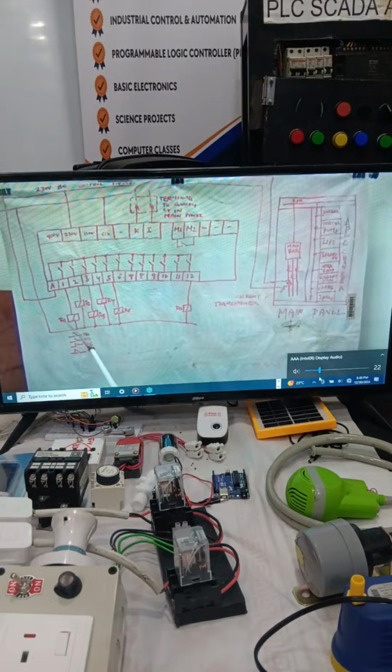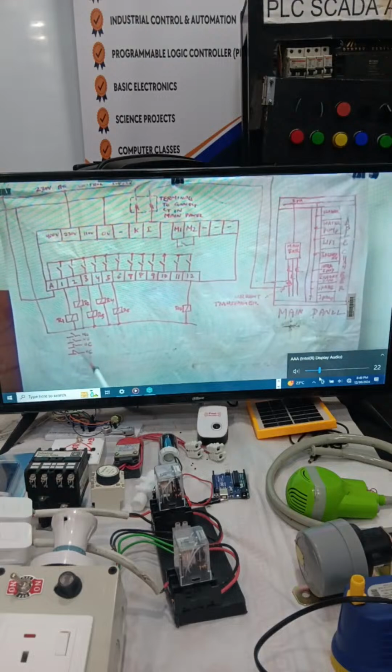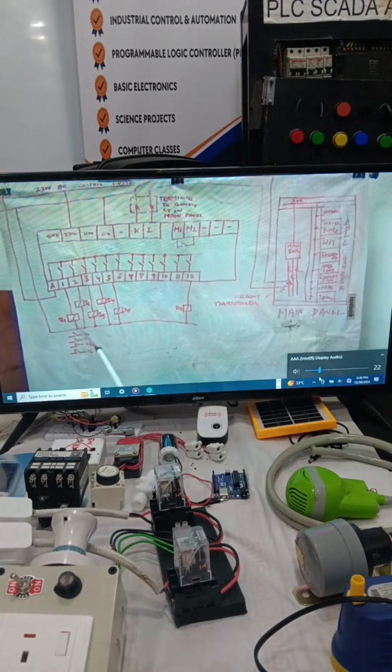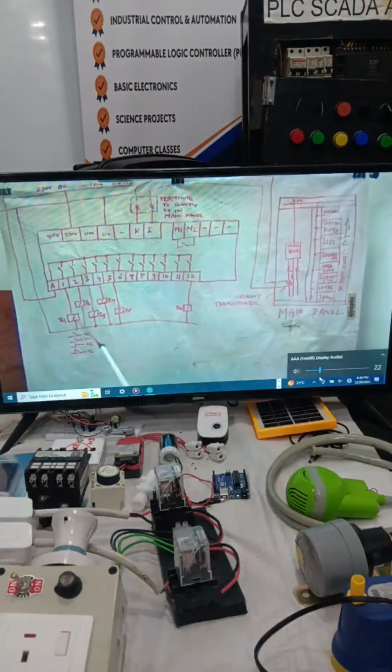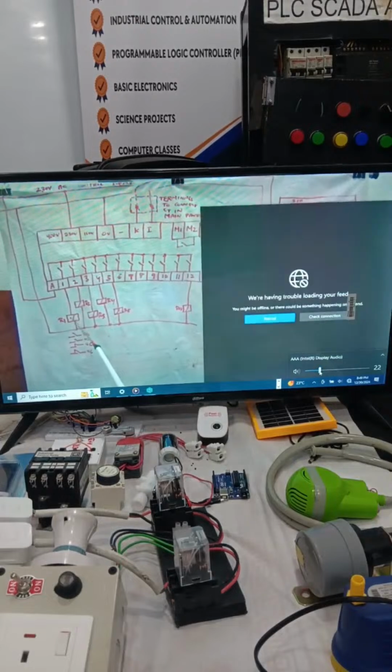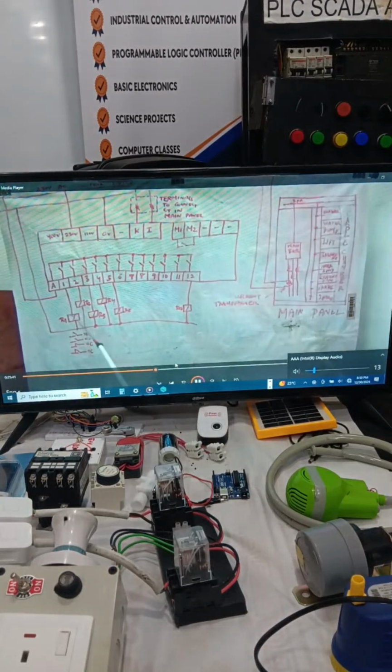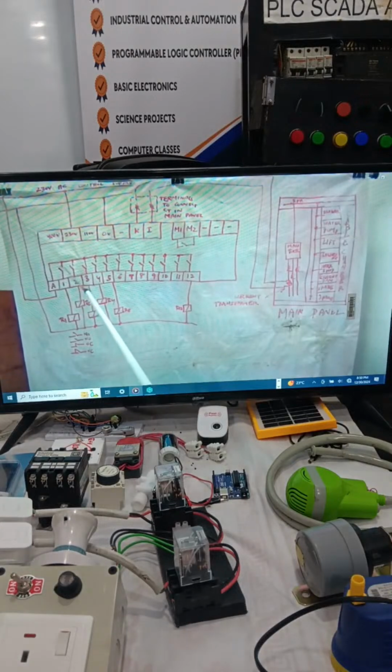In some cases, if the contactor size is small, it directly feeds the contactors. But if the contactors are big, or there are more contactors, like in our case where we have 3 contactors in parallel, the load comes to this point. In that case, this contact will burn, and since it is inside the contactor, we can repair it.